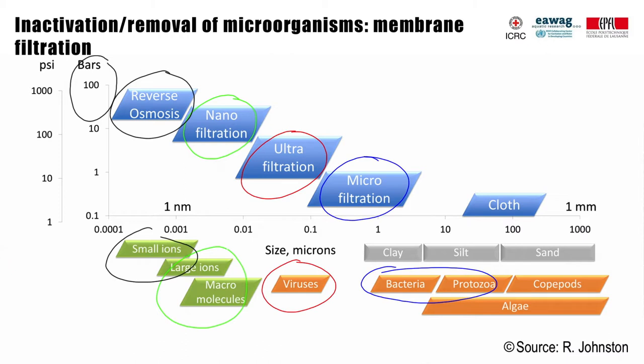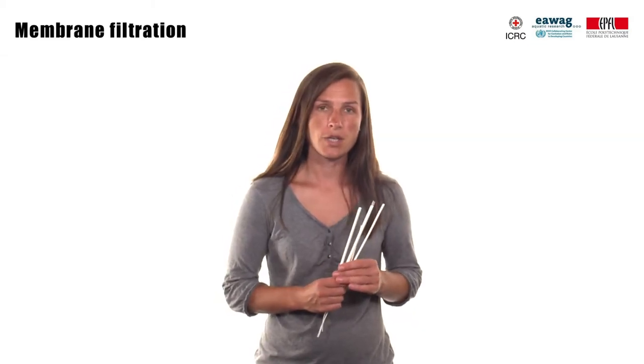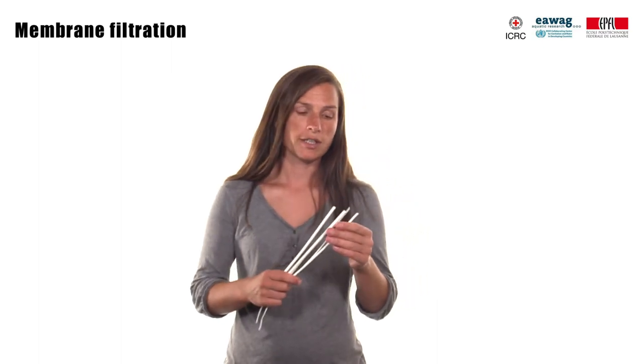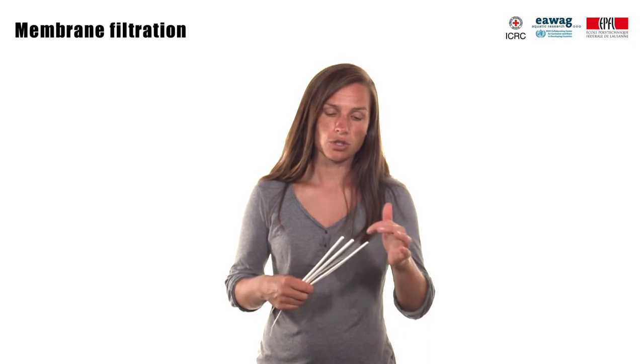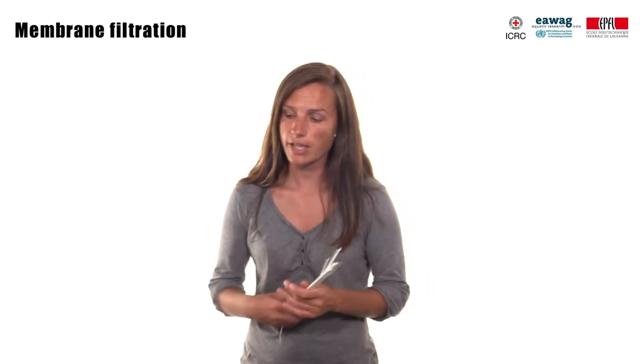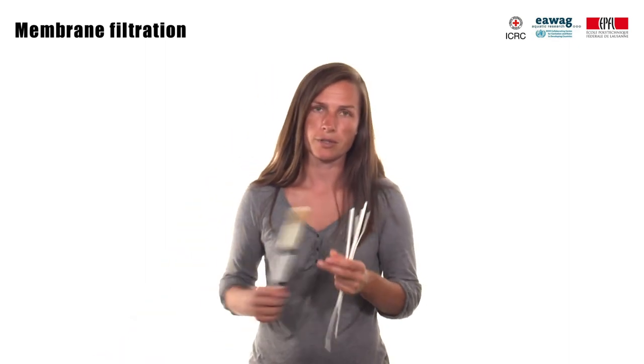For disinfection purposes, ultrafiltration membranes are most common as they are effective against pathogenic microorganisms including viruses and particles. Different configurations of membranes are available. In drinking water supply, hollow fiber membranes are commonly used. They can have different diameters and configurations. The water usually goes through the membrane from the inside and passes out the other side. They can also be bound together in a bundle to achieve a high surface area.